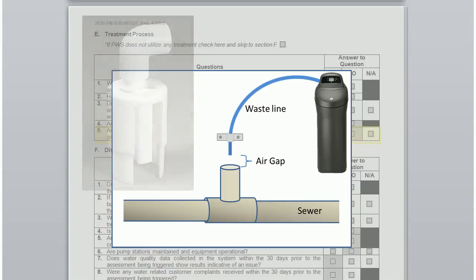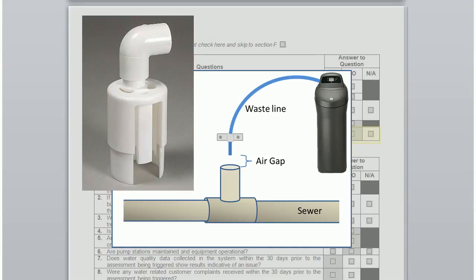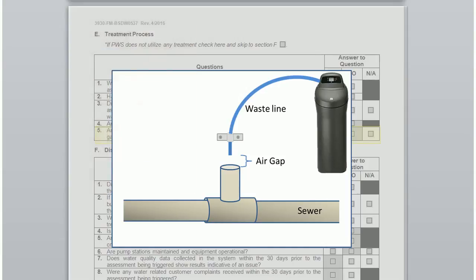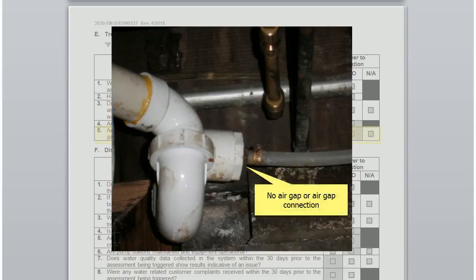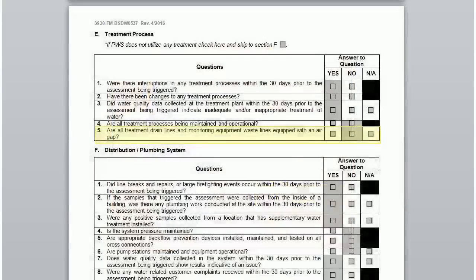There are connections available that provide the necessary air gap, such as the one shown. Air gaps must be at least twice the diameter of the supply line. So if you have a 1-inch diameter drain line from the softener, the air gap must be at least 2 inches. Shown is a picture of a drain line without an air gap. Check NO if any waste drain line does not have an air gap.